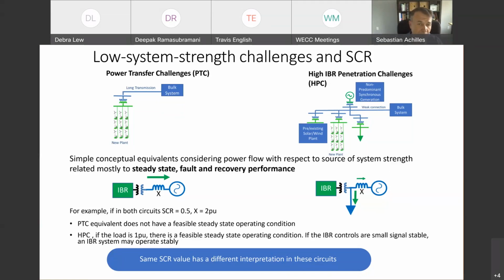The system on the left just doesn't work. It's just not possible to push 1 per unit power through a 2 per unit reactance. There is no possible steady state point of operation where you can have the system working stably. So that's why the industry is mostly focused on the problem on the left, and it's very unusual to talk about short circuit ratios as low as 0.5. And it doesn't matter what type of IBR we're talking about, there is no possible way of operating that.